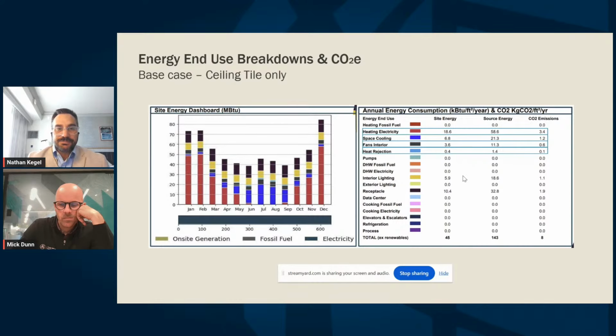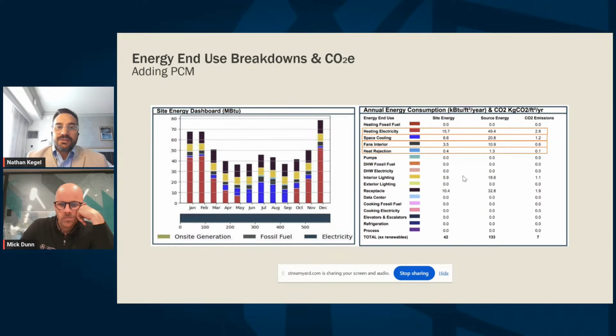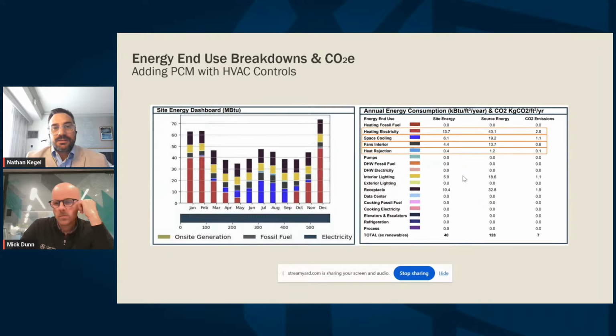If you go to the next slide, you see that the heating electricity goes down, the cooling electricity and fans start to creep up. And on the last one, the heating continues to go down while the fans come up slightly. So the strategy here was to expand the operation of the fan, to leverage that phase change more, moving more air across it so we can get better heat transfer. That's a much more energy efficient strategy than running the boiler or the air conditioner.